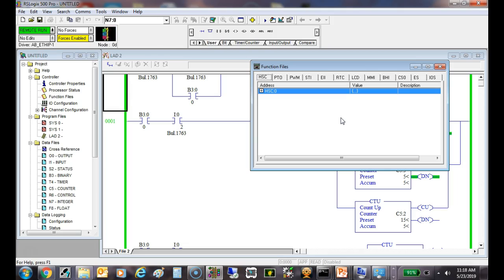So the big advantage hardware has over software is hardware has the ability to always be faster. So what was happening was they would take these software counters and they would try to hook them up to encoders, which are the spinning thing that's on motors where they can get the speed and position. And the software counters just couldn't keep up with those things. So what they started to do, guys, is they're starting to put hardware counters, literally circuits inside the PLCs that are hardware, and they call these high-speed counters.